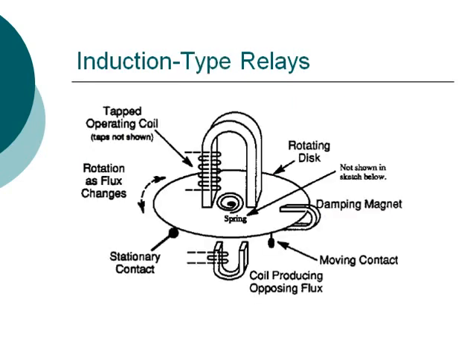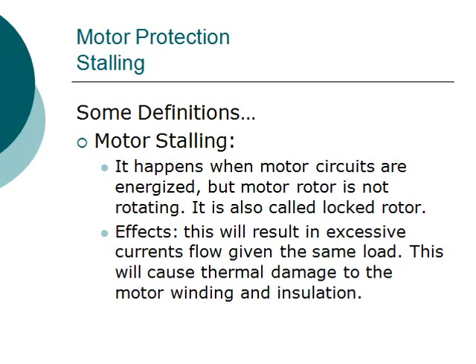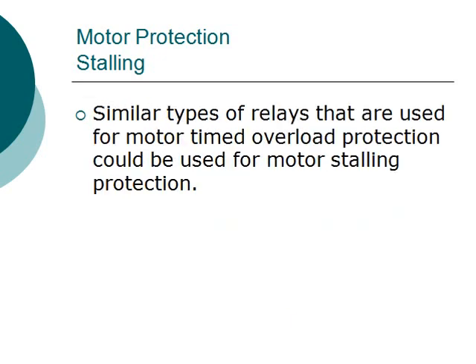Motor stalling protection: motor stalling occurs when motor circuits are energized but the motor rotor is not rotating — this is called a locked rotor. This results in excessive current flow, which causes thermal damage to the motor winding and insulation.